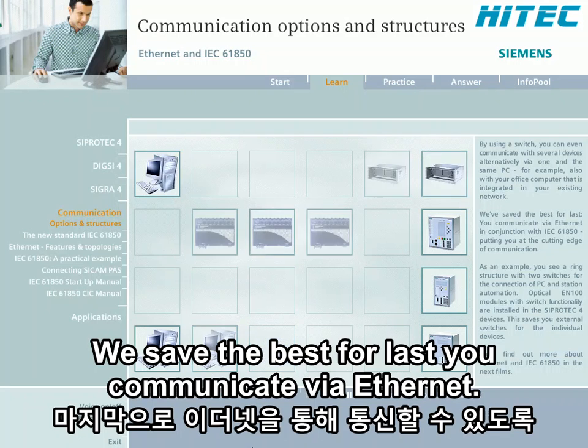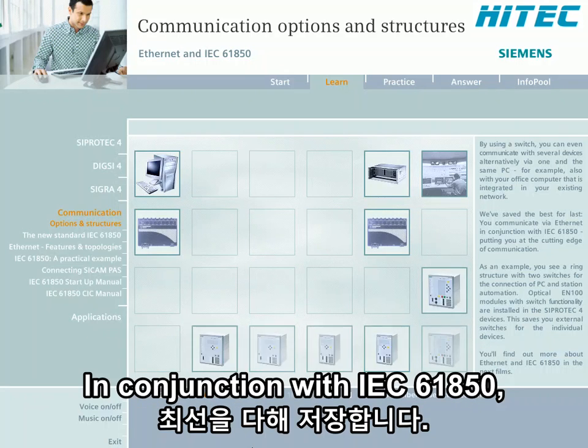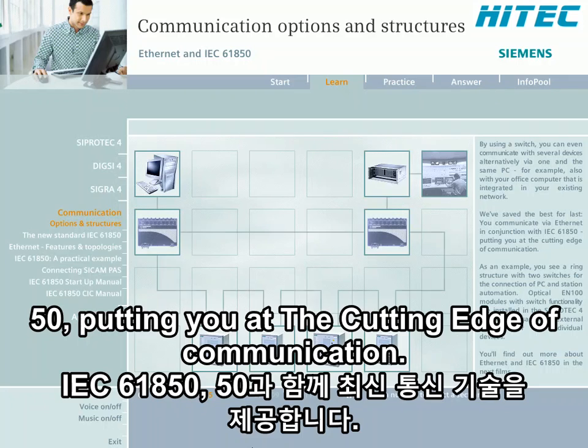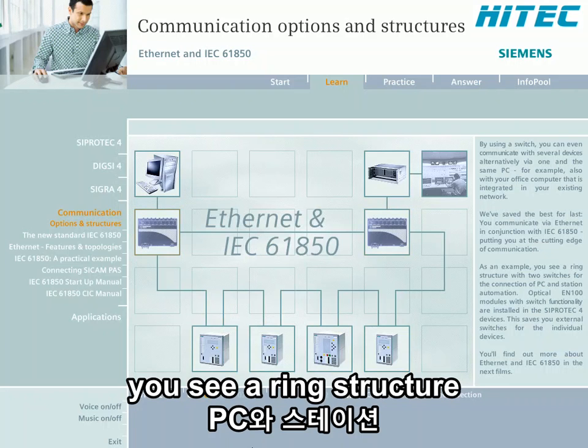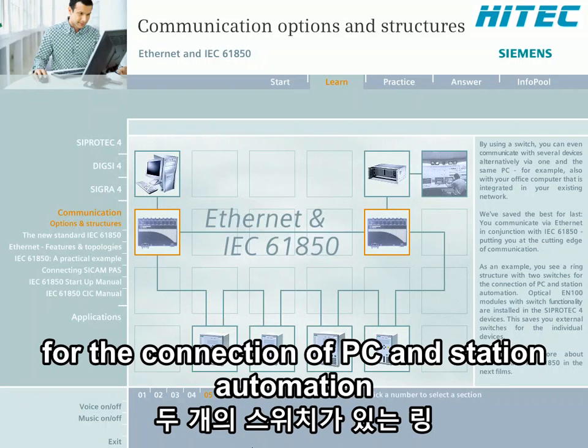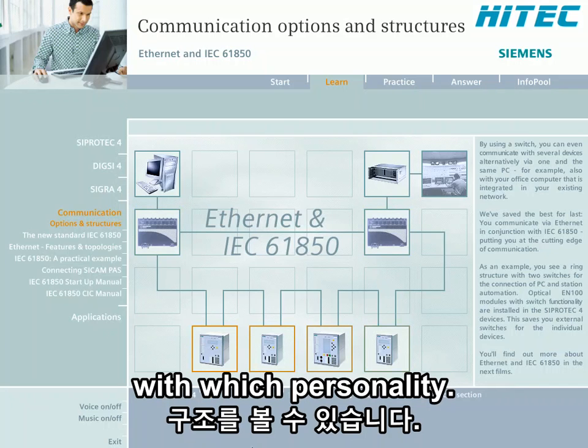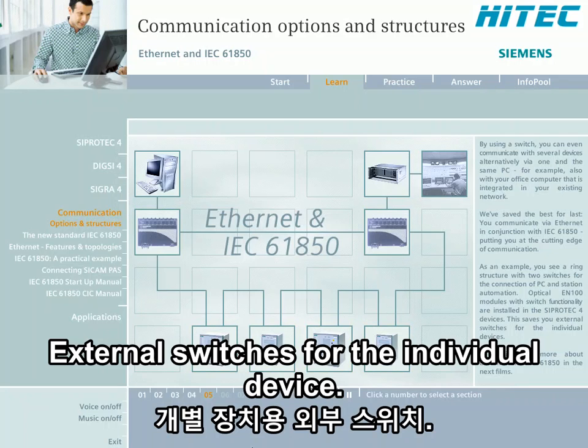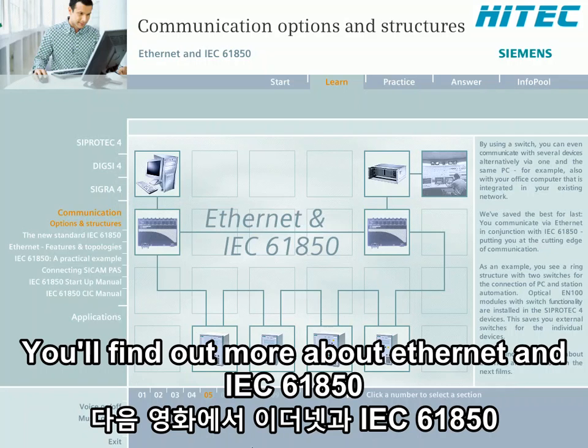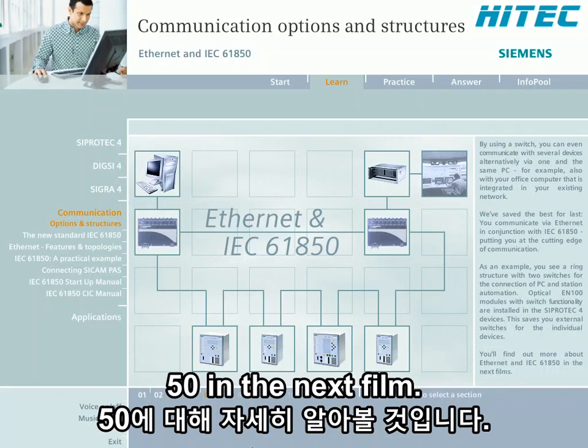We saved the best for last. You communicate via Ethernet in conjunction with IEC 61850, putting you at the cutting edge of communication. As an example, you see a ring structure with two switches for the connection of PC and station automation. Optical EN100 modules with switch functionality are installed in the SIPROTEC 4 devices. This saves you external switches for the individual devices. You'll find out more about Ethernet and IEC 61850 in the next films.